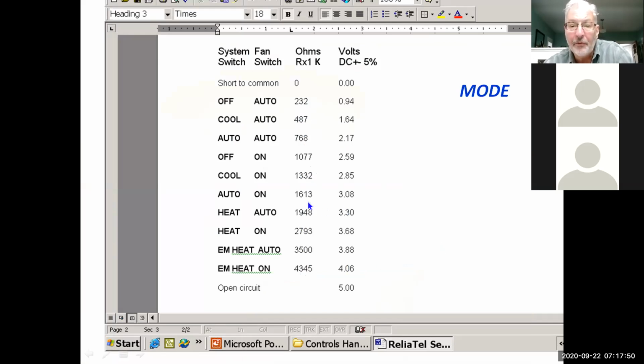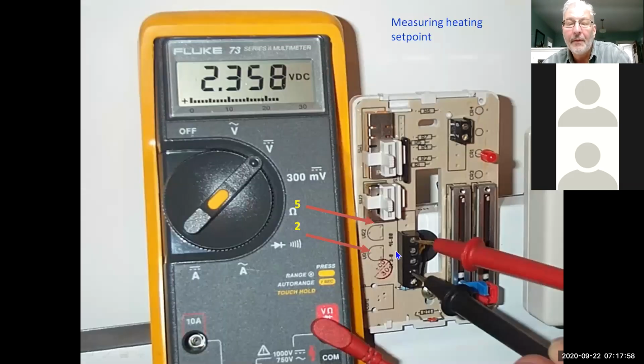The nice thing with this is you can do it from the rooftop. You don't have to be in the space to see what's going on. If you take these readings, you can do it right from the rooftop. Now, if you want to measure the heating set point, that's between terminal 2 and 5. Okay, again, 2 is common, 5 is going to be your heating input.